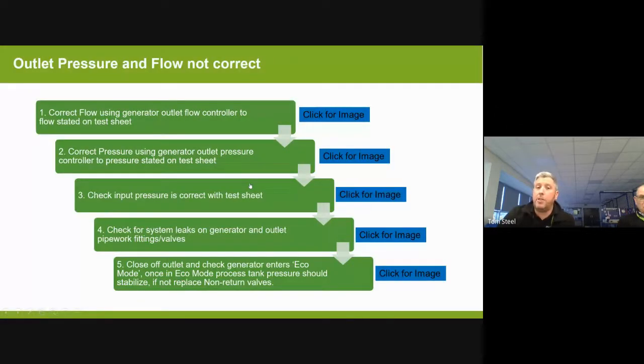Correct pressure using the generator pressure outlet controller, using the test sheet. There's a test sheet right there, and that details all the information that's required to ensure that the purity of the gas is maintained. We don't want to go higher than what the test sheet is telling us. We just work to that test sheet.